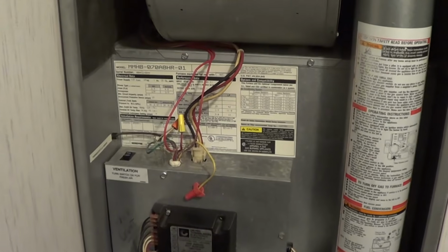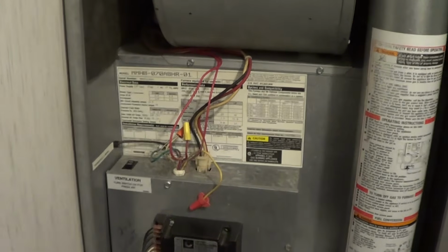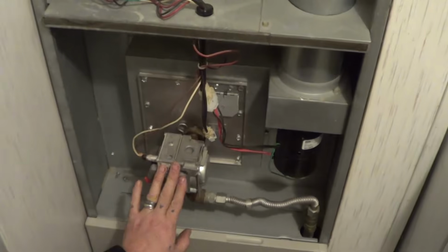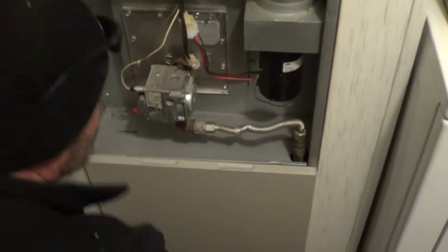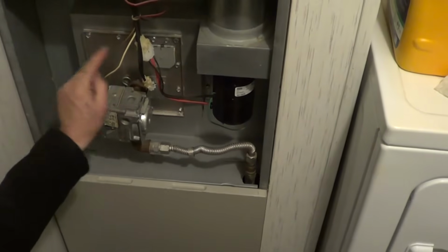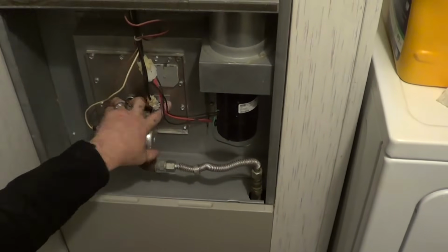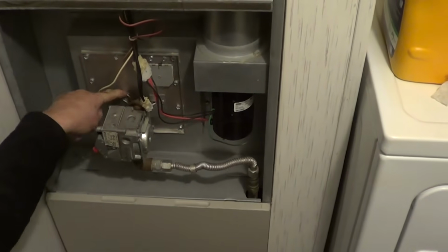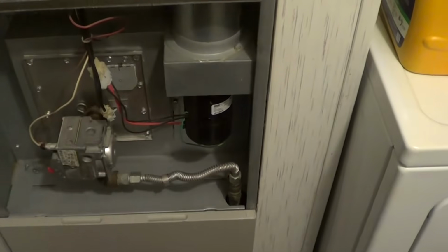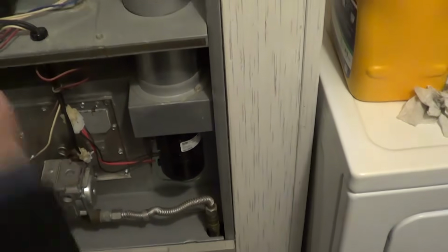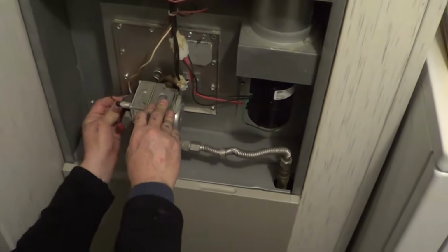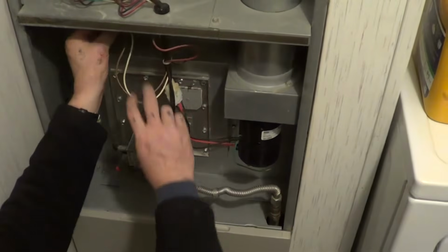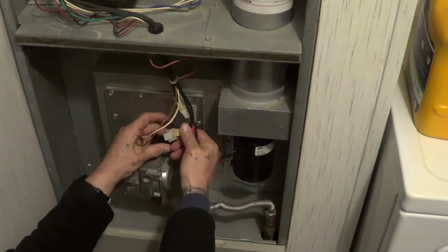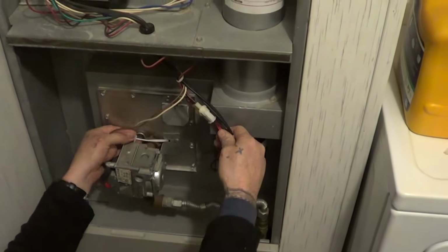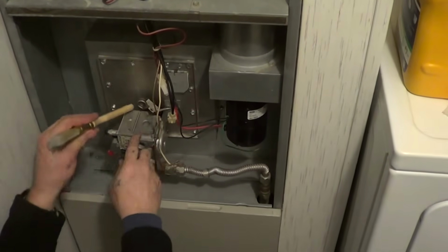Okay, so we have an MMHB, and to get there, we're going to need to get this valve off or replace this valve. So in order to do that, we need to take all of these screws off here, and this one right here, and we need to take this pin out right here. Do you see that? So we'll also need to disconnect a few things. First off, we make sure that the power is off up high there, and we're going to take the 2 power wires to the gas valve off here, and it doesn't matter which way those get put back on. And we're going to disconnect the igniter there. So pretty straightforward. And then we're just going to grab something to pull this open.